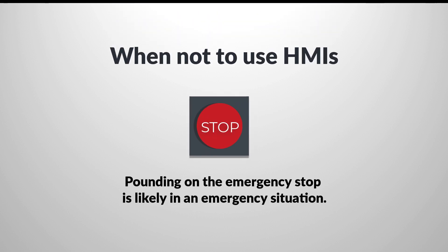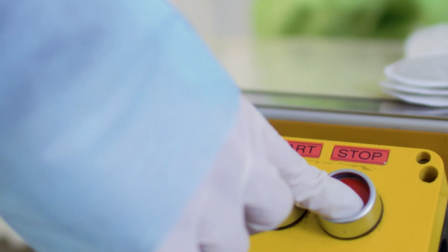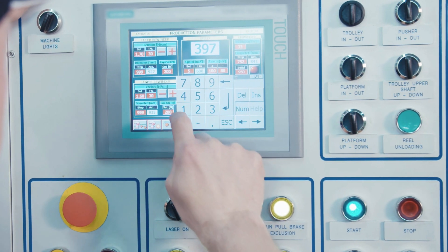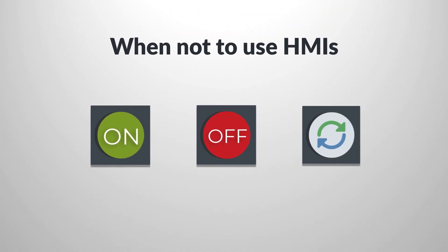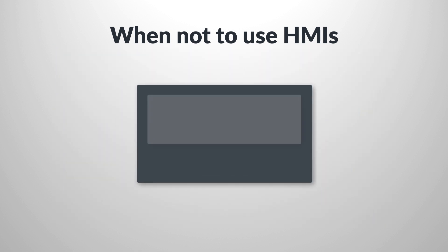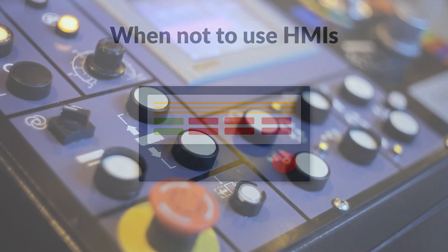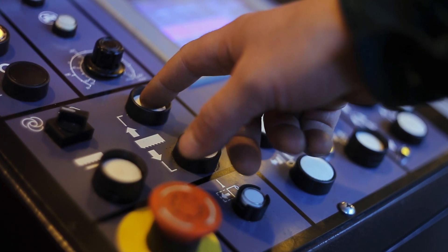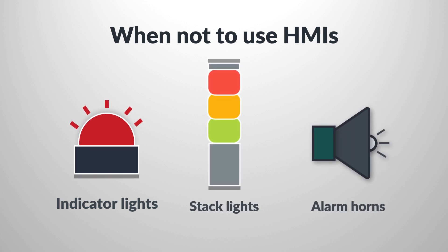Pounding on the emergency stop is likely in an emergency situation — it cannot be a button on the HMI screen. Safety standards require it to be a hardwired push button. Some will argue that with advances in HMIs and computer graphics, machine power on, power off, reset functions, all fault indication, machine status, and operation can be provided on screen. While the HMI can do it all except the emergency stop, it's not always the quickest or most robust method of operation during production. Sometimes the use of push buttons that are poked often, and indicator lights, stack lights, and alarm horns are better options. These devices can greatly reduce the response time to a machine fault condition and provide machine status information at a glance or without looking.